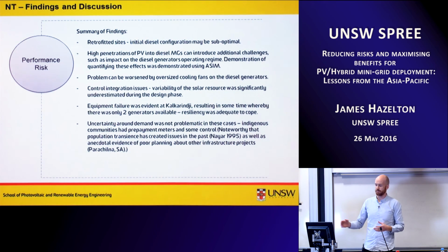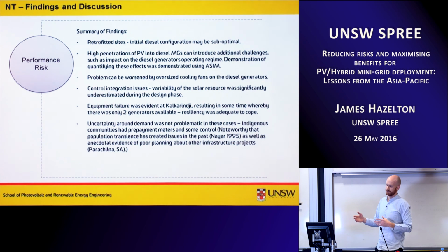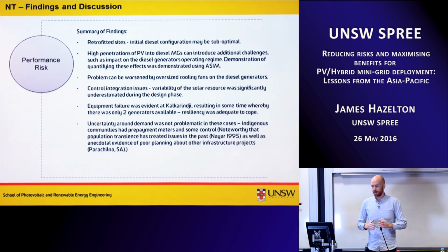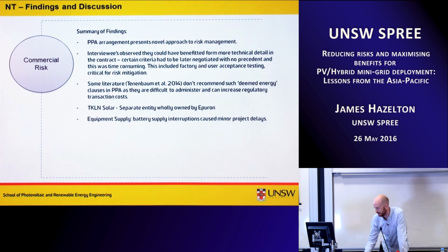But there have been documented examples in the NT previously regarding the transience of indigenous communities that might move on, or in the case of Parachilna, they'd upgraded to a solar diesel system in the early 2000s. I can't remember the exact date, but just after they did that, the pub put in a backpackers and a water treatment plant as well. So the original design load changed dramatically, and that resulted in additional battery deratings, or - what's the term - depth of discharge, shall we say.